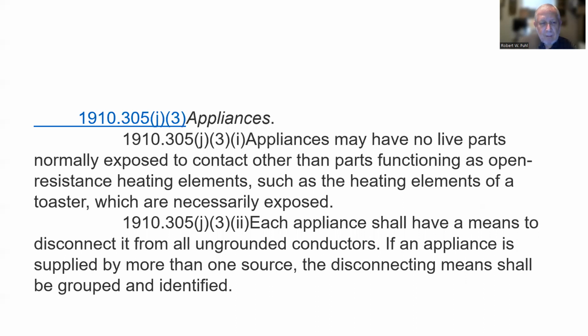Appliances may have no live parts normally exposed to contact other than parts functioning as open resistance heating elements, such as the heating elements of a toaster, which are necessarily exposed. I was always taught to not stick my fingers down in a toaster. And I still obey that to this day. I still don't do it. So each appliance shall have a means to disconnect it from all ungrounded conductors. If an appliance is supplied by more than one source, the disconnecting means shall be grouped and identified. So if you got a whole bunch of toasters, all right, we're gonna go there. But that's good that they put something in there and they give you an example, which is a good example of an appliance that has exposed electrical parts, the heating elements.